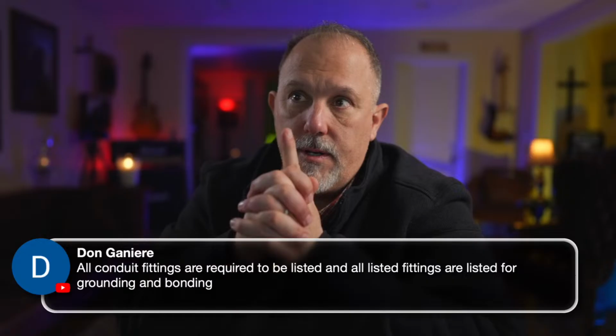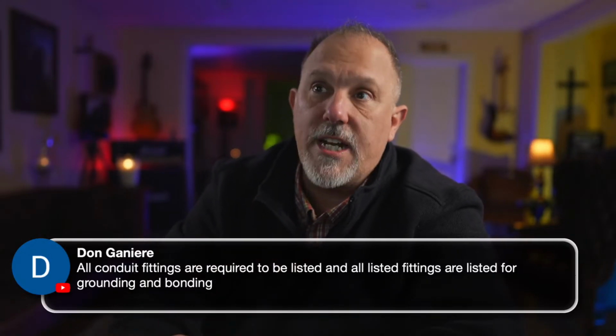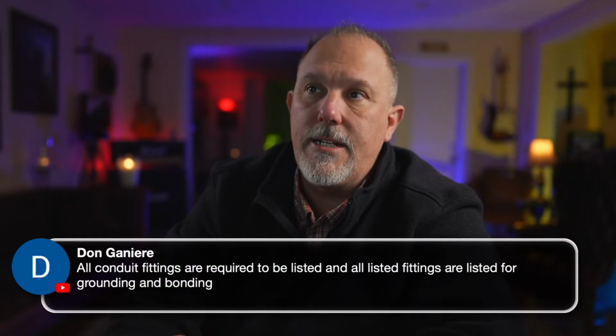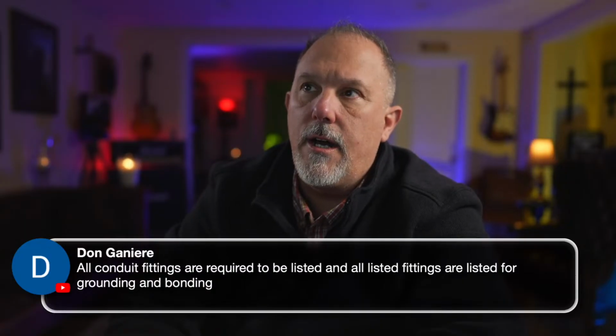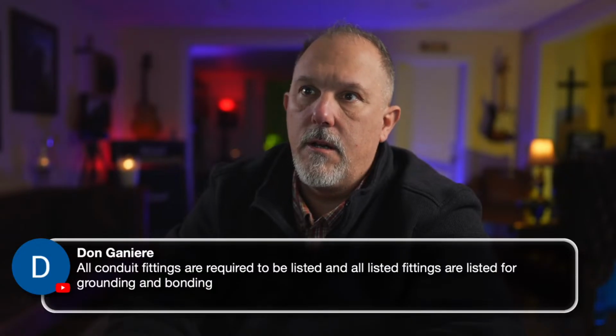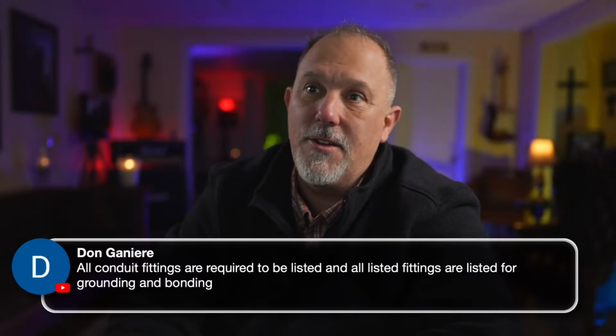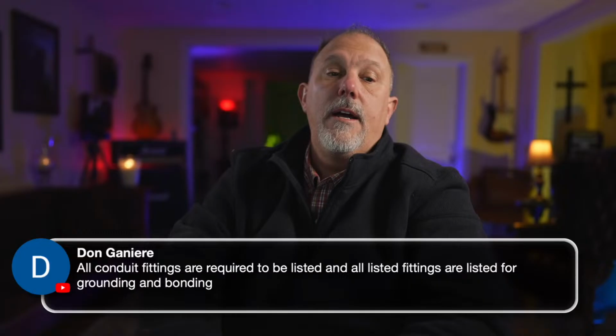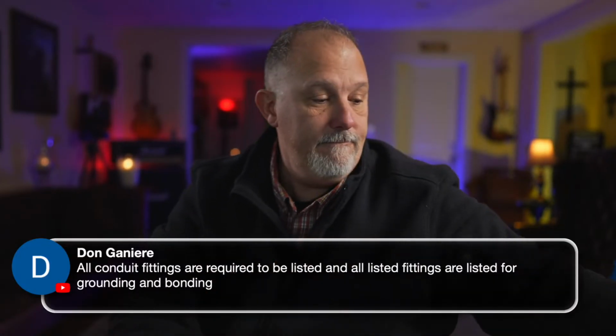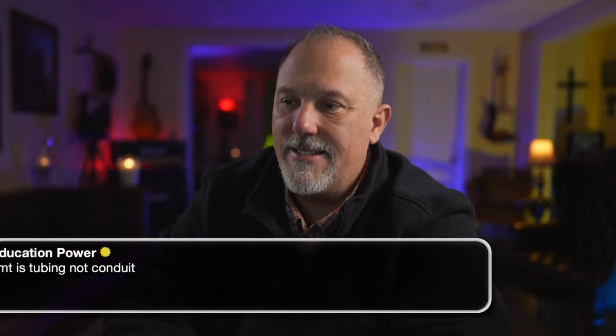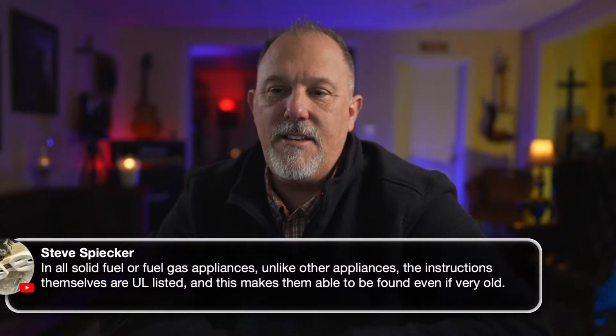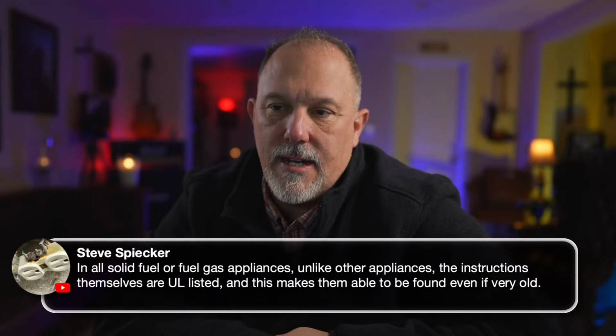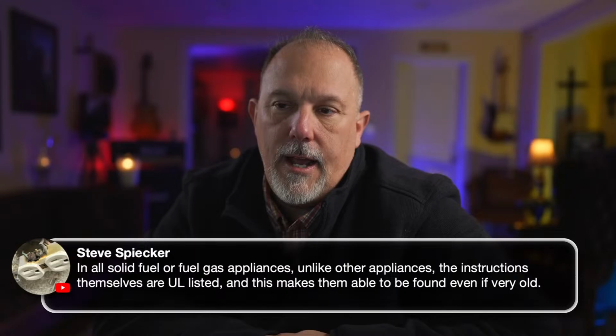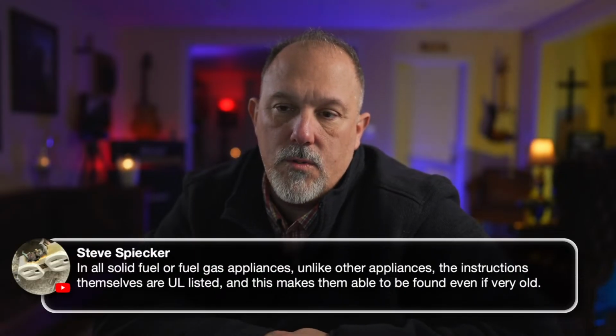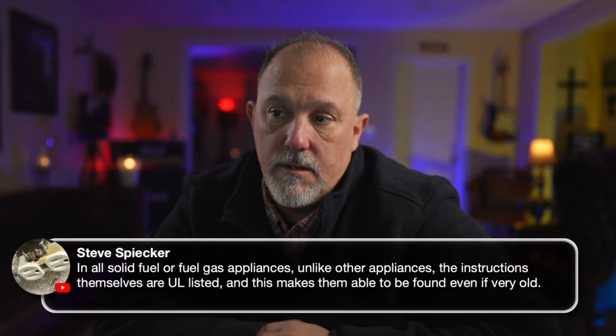I probably did not use that one, and the other one, oh no, I did use the zinc-plated steel coupling. Let me see if that says UL listed. Yeah, UL listed for dry locations. So, see, Dawn? I did an overkill. I spent a little bit more money than I should have. Look at that. EMT is tubing, not conduit. I love it. Steve, in all solid fuel or fuel gas appliances, unlike other appliances, the instructions themselves are UL listed, and this makes them able to be found even if very old. Oh, interesting, Steve. Very interesting. I like it.